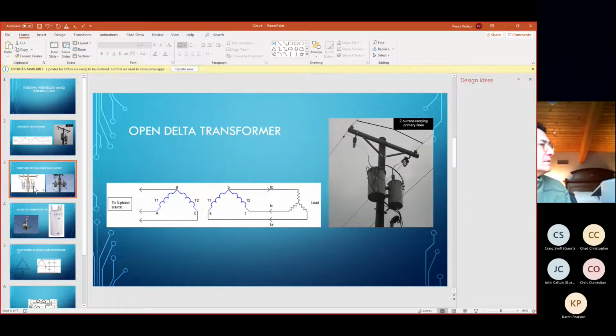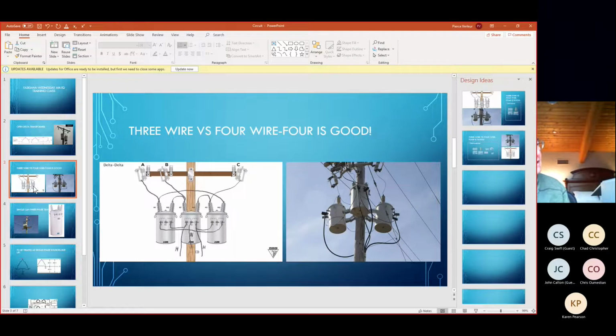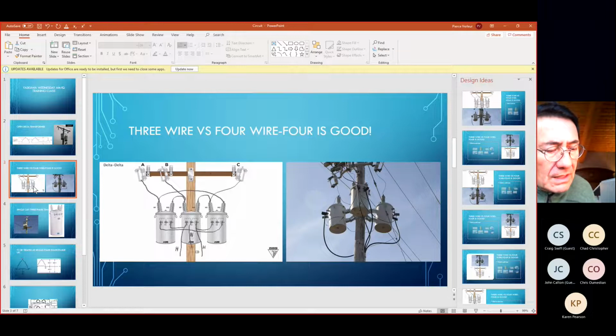What we want to see is a 4-wire situation. Again, a couple of power pole pictures, and there's all kinds of variations out there. But one thing I would like to say is that it's really important that you look up at the power pole when you make an installation. It's critical that we understand the power pole configuration for obvious reasons. Here we've got an acceptable 3-can situation with critical 4 conductors coming off this thing.